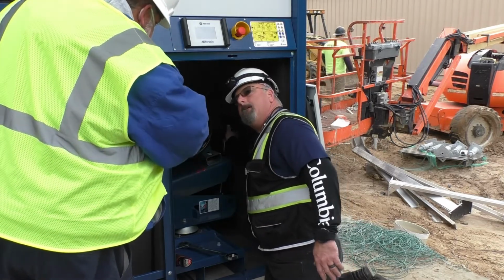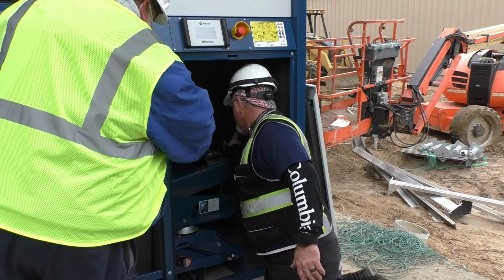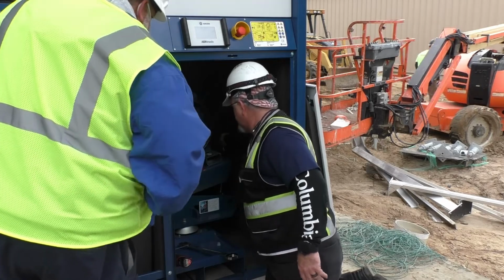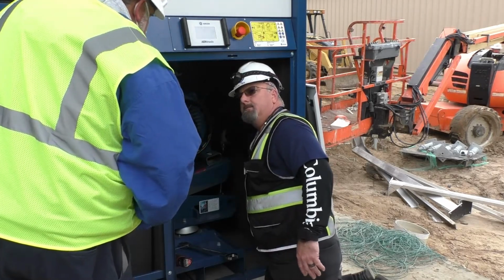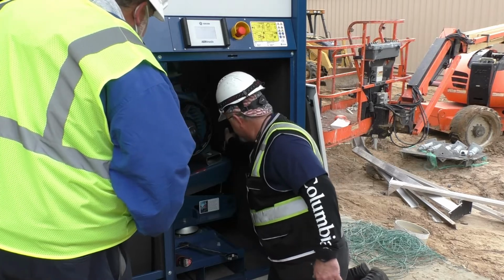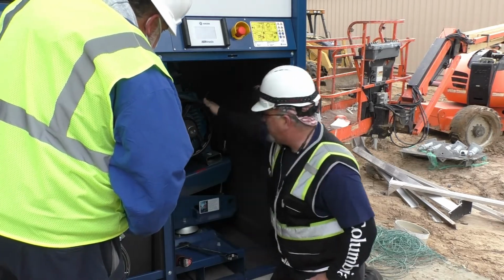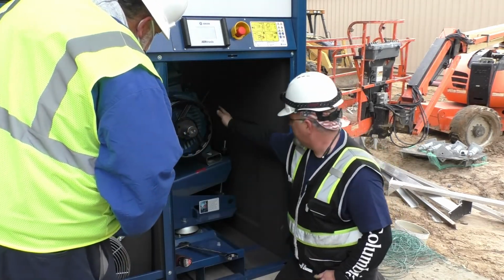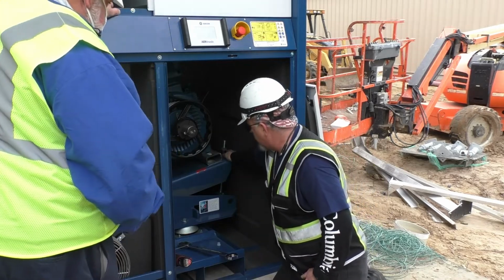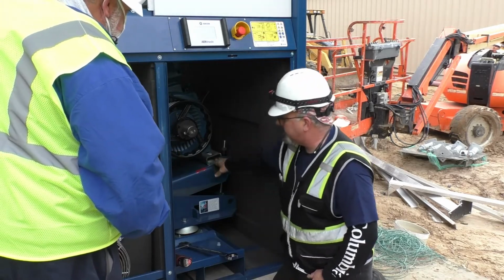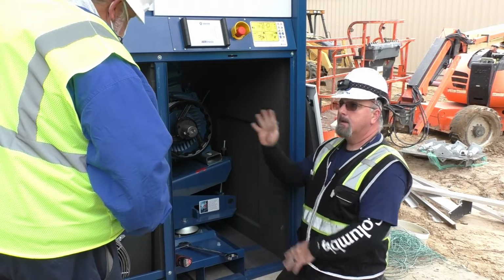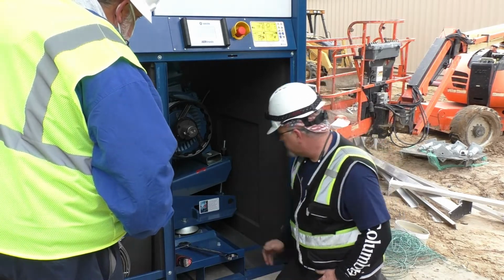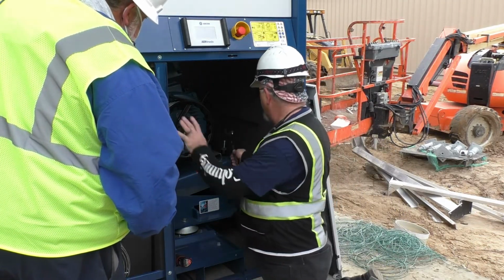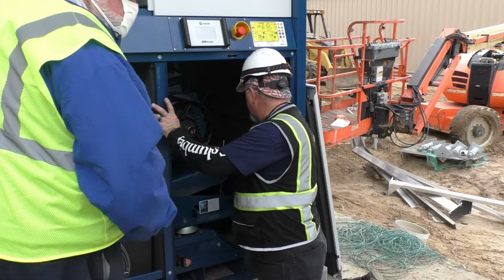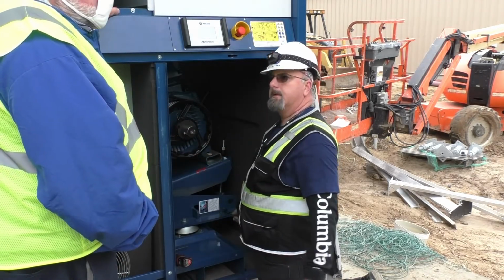That doesn't lock down. It's always going to have tension from the motor weight, right? This should always move. It should move just like that. That's what keeps the belt in tension, is the weight. The weight keeps the tension, yes. And this, at this point, serves to prevent this motor plate from just slamming down if you were to break belts. And it also provides, when needed, your ability to lift it up.